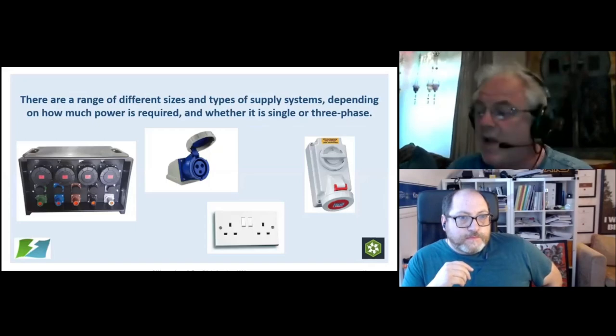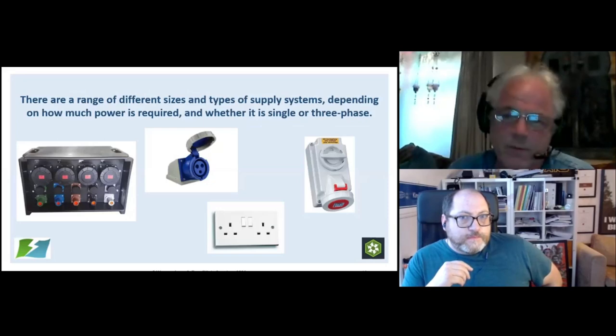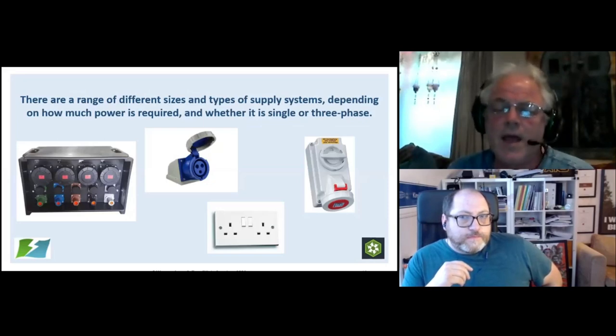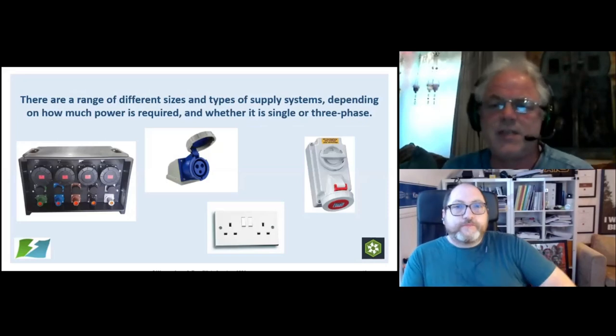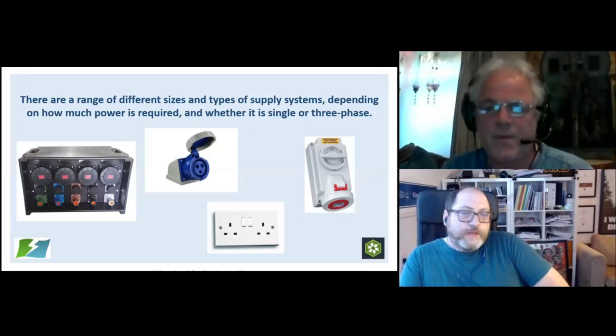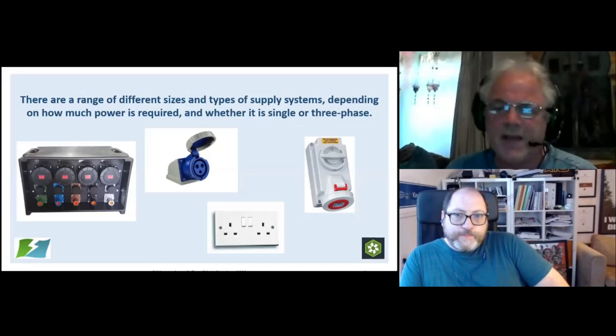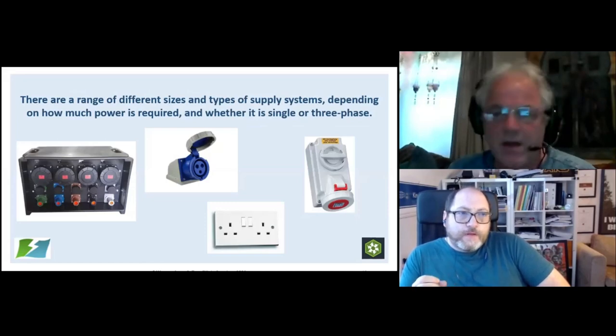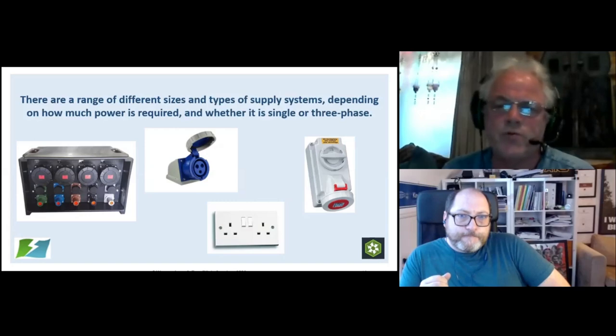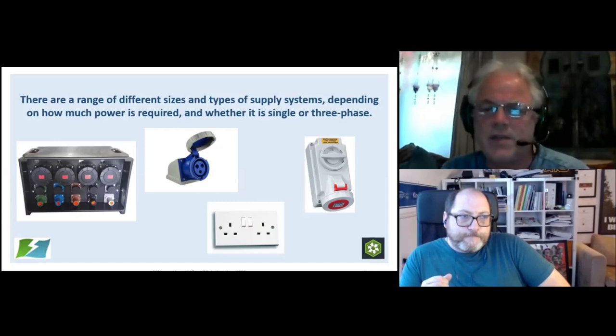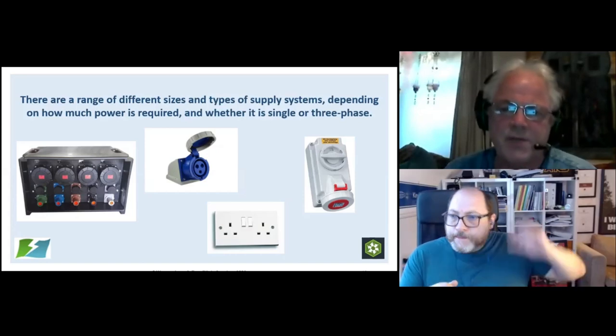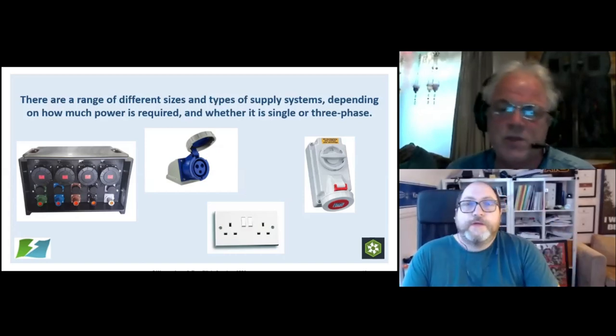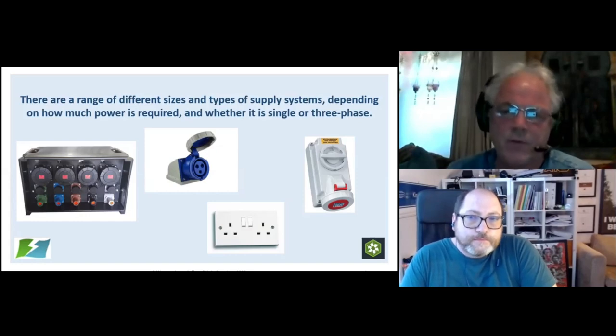So we have a range of different sizes and types of supply equipment depending on how much power is required and whether we need single phase or three phase, and we tend to standardize on 16 amp, 32 amp, 63 amp and 125 amp CEEform for getting the power around. For larger sets of power, we use powerlock, at 250, 400 amp, three phase. We can use smaller extension leads if we want to drop down from a 16 amp down to a 13 amp extension lead. There's no reason why we can't if we're using it indoors. If we're using it outdoors, then obviously everything's got to be weatherproof to IP44 as a minimum.